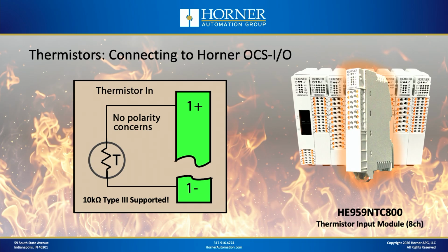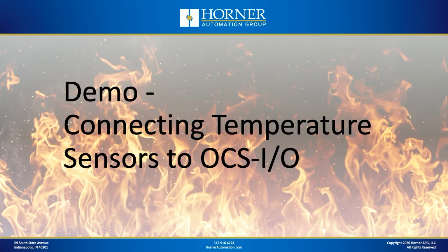In terms of connecting thermistors to the Horner OCS-I/O family, because it's got a wildly different ohmage range than we're talking about with RTDs, we have a dedicated module for thermistors. So it's an 8-channel thermistor input module, which we're just releasing this month, which is why we've got this video timed when it is. And it's an 8-channel thermistor input module where you can basically connect, again, either side of the thermistor leads to either terminal for each channel. And it basically supports type 3 sensors, is the type of sensors that are supported by our thermistor input module. Okay, so hopefully that was a good overview with some detail there on thermocouples, RTDs, and thermistors.